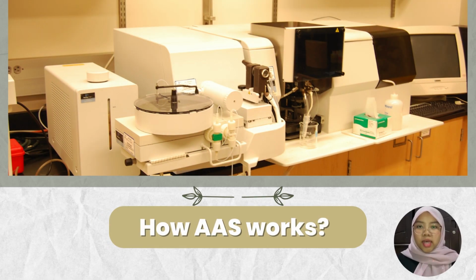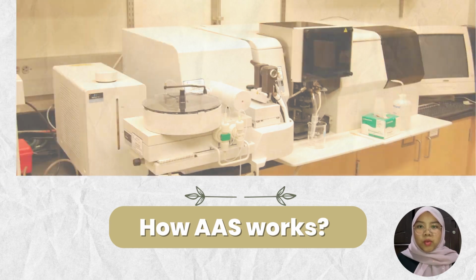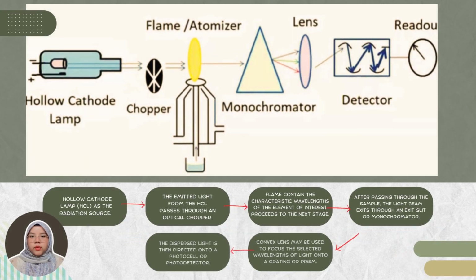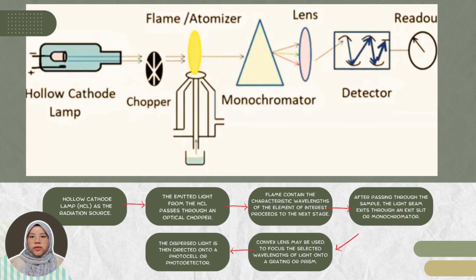Now, let's take a look at how atomic absorption spectroscopy works. The process begins with the hollow cathode lamp, HCL, as the radiation source. Then the emitted light from the HCL passes through an optical chopper. It chops the continuous light beam into pulses. The flame containing the characteristic wavelengths of the element of interest proceeds to the next stage.